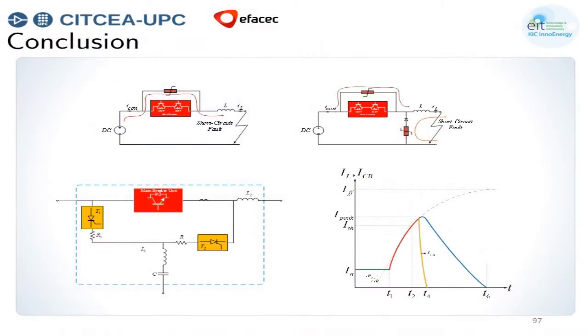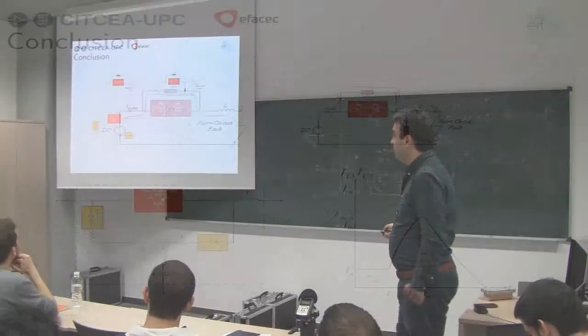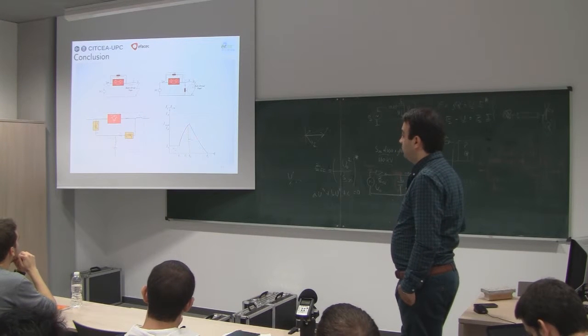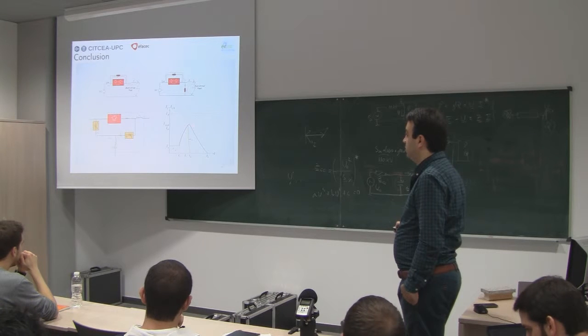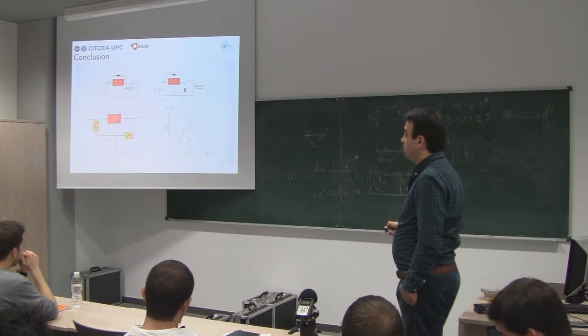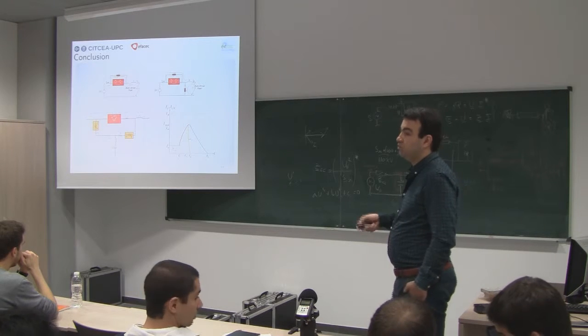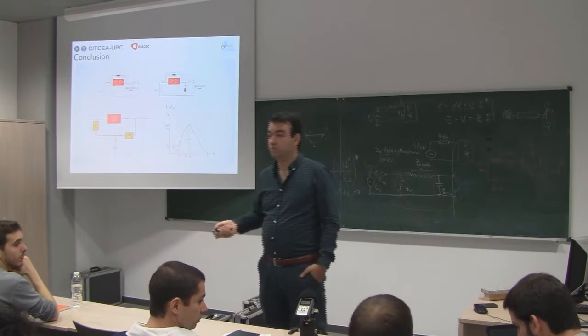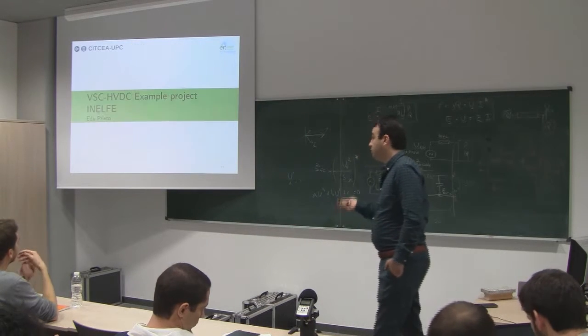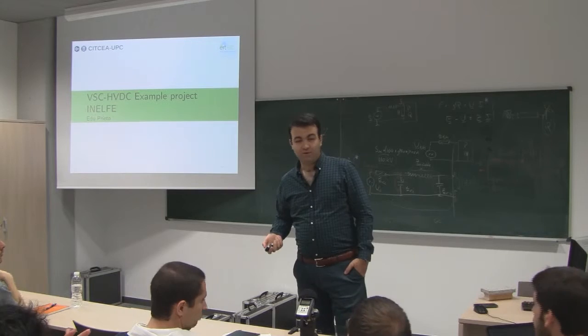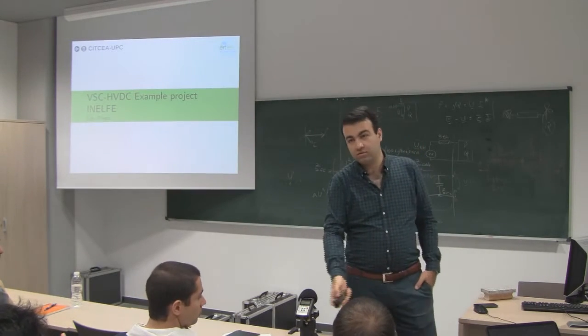So, this is the conventional topology for a solid state circuit breaker. You can see you have the parallel surge arrestor branch. So when you are opening this, the current is still flowing through this parallel branch to be damped. If you suppose the interruption curve for current for these topologies, like this blue one, for the topology that I introduced, it will be like this one. So it is much faster, even compared to the conventional solid state circuit breakers, in terms of isolating the fault current from the converter.